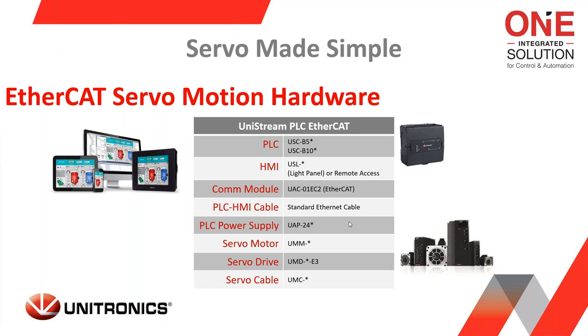And then for your servo motor, you would want to look at the UMM series of servo motors. Pick out the motor that will fit your torque requirements and your speed requirements. It will help you determine what servo drive is needed. And the servo drives are the UMD series that end in the nomenclature -E3, EtherCAT 3. And of course, you will need cables to connect the motors and the drives. If you were to pick your PLC, the HMI model, your power supply, and then your servo motor, drive, and cable, you have a fully functioning EtherCAT-based servo motion system.